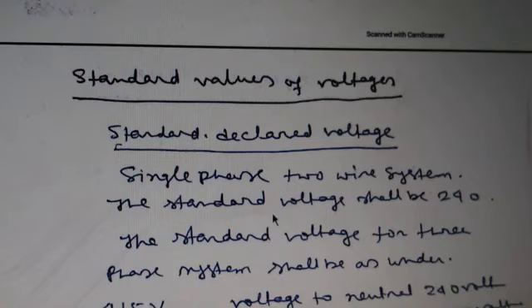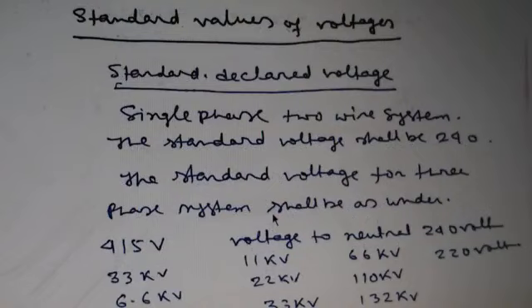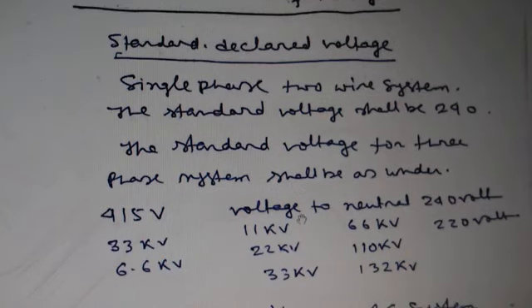In case of voltage above 1 kV, the importance of highest system voltage, which is generally 10% above the corresponding nominal voltage given below, is recognized, and the standard voltage rating of equipment is with respect to the highest system voltage only. Now, the standard declared voltage. Single phase 2-wire system, the standard voltage shall be 240 volts.